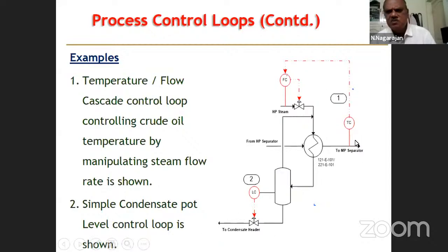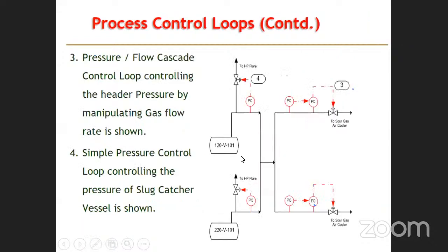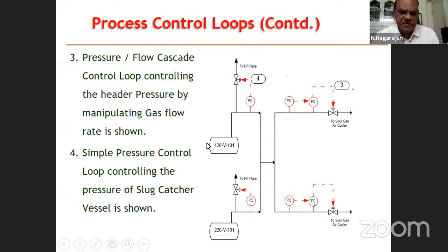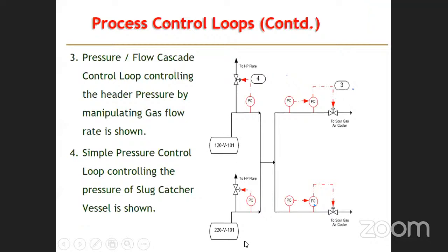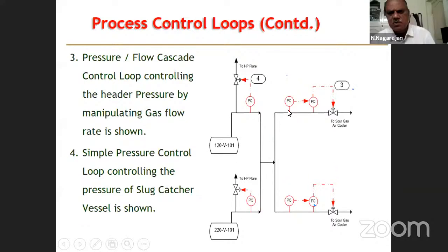So here the main thing is you measure the temperature of the output crude oil, then regulate the steam flow to the exchanger. Okay. On the condensate pot, level control is used to regulate the drainage. And the control becomes more complex when you have more equipment. Here you can see there is pressure control in one vessel and pressure control in a second vessel. The combined stream is going, and again they are divided into two streams. You have flow control in each stream, but the configuration is the same.